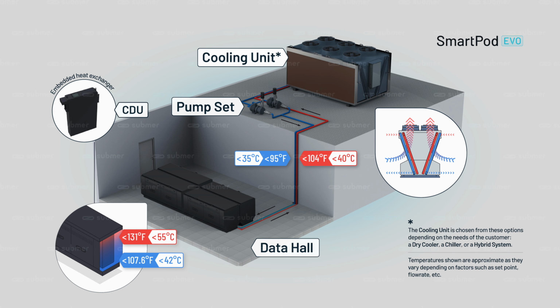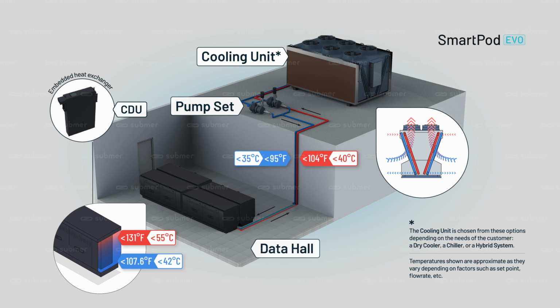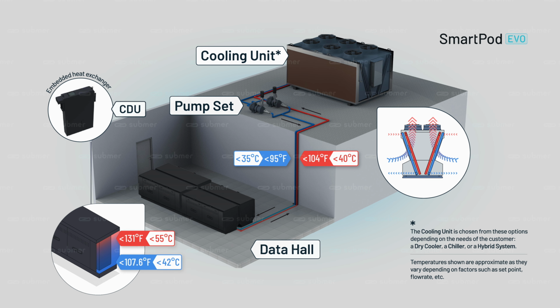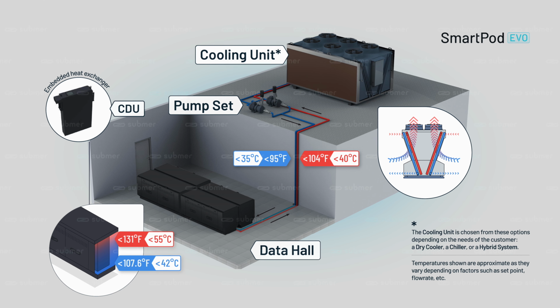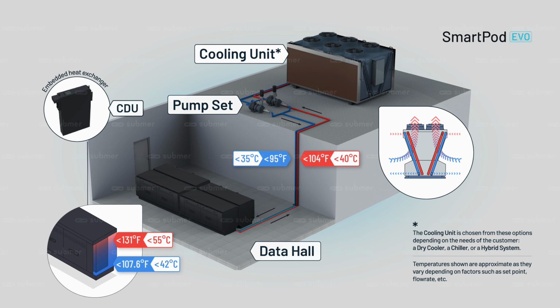Immersion allows us to run high-density compute systems with very warm water, which means we don't have to produce cold water. By not having to produce cold water, we can use dry cooling technology, basically giant radiators that sit outside the data center. Our systems today can operate with 32C and even 40C water supply in some scenarios, which means you can run this dry cooling infrastructure all year round in a lot of locations on the planet.